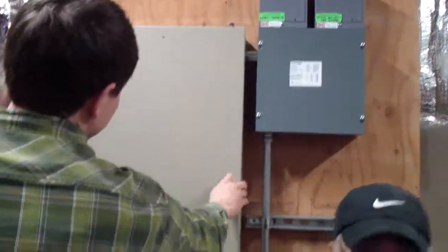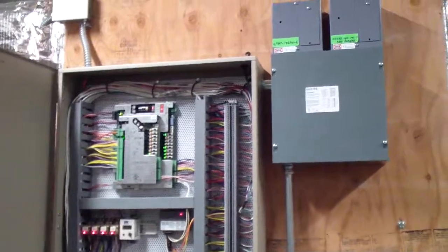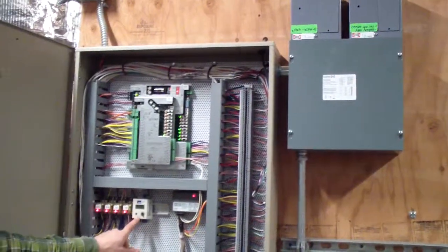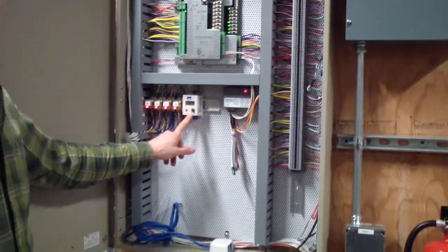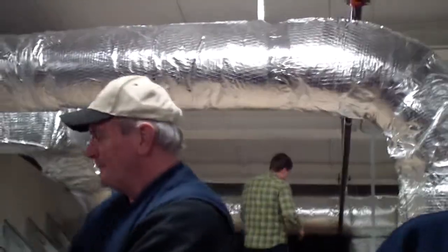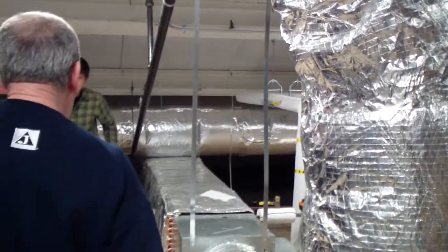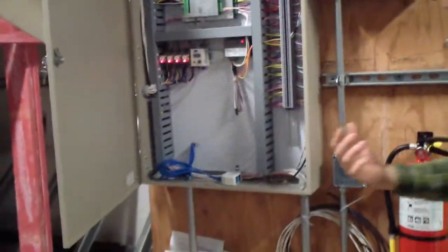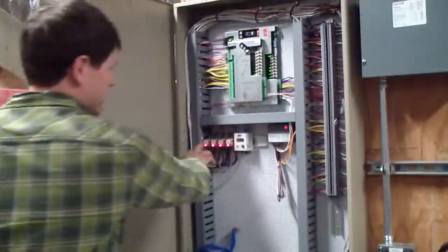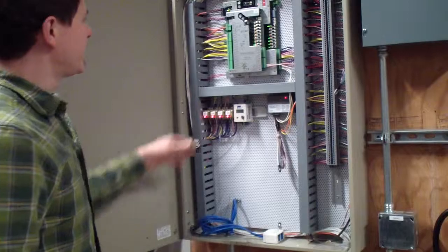This is the controller for the unit itself. You've got this is your duct static sensor, where the probe for it is actually punched into the ductwork over here. Nothing real fancy to look at, it's just a pneumatic tube that they strung out across the ductwork and punched it in. It monitors that versus ambient air. These are your safety relays. And then this is your board.